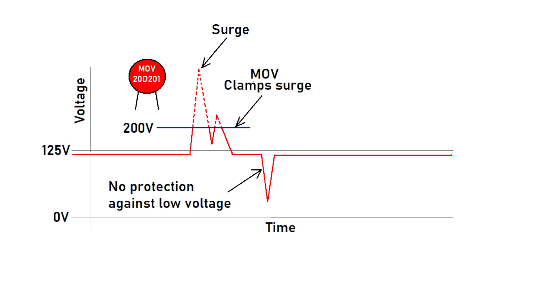You can think of an MOV as a voltage controlled switch. In the drawing here, we see an MOV that's rated for 200 volts, and any surges above 200 volts will be sent to ground, thereby protecting the circuit.